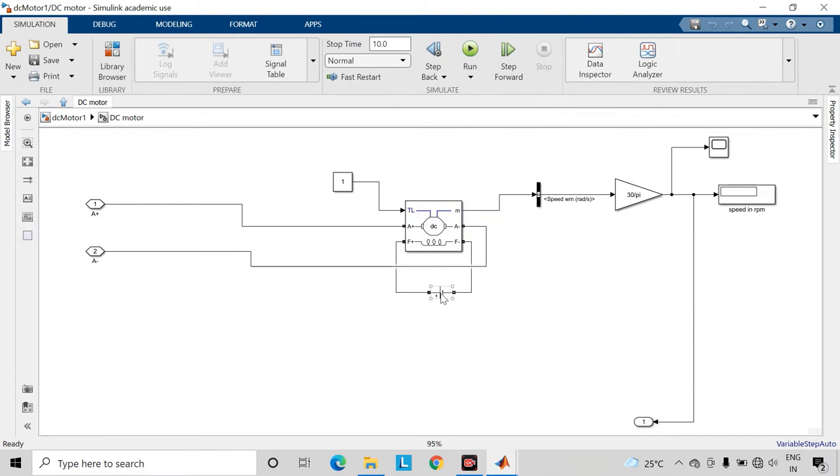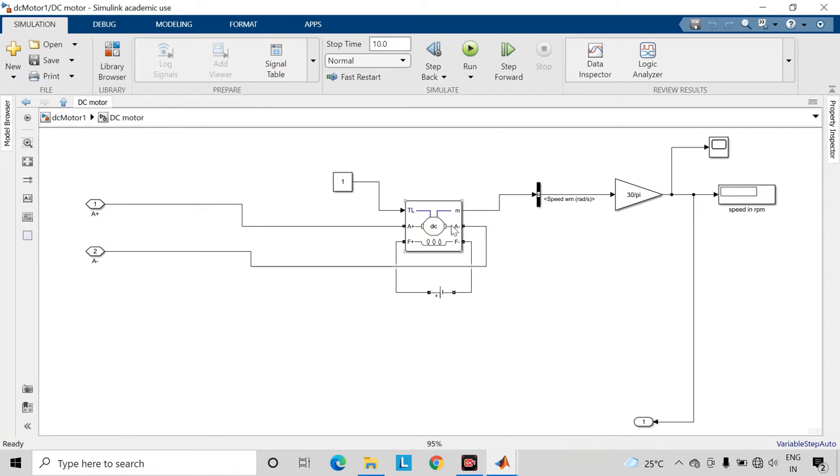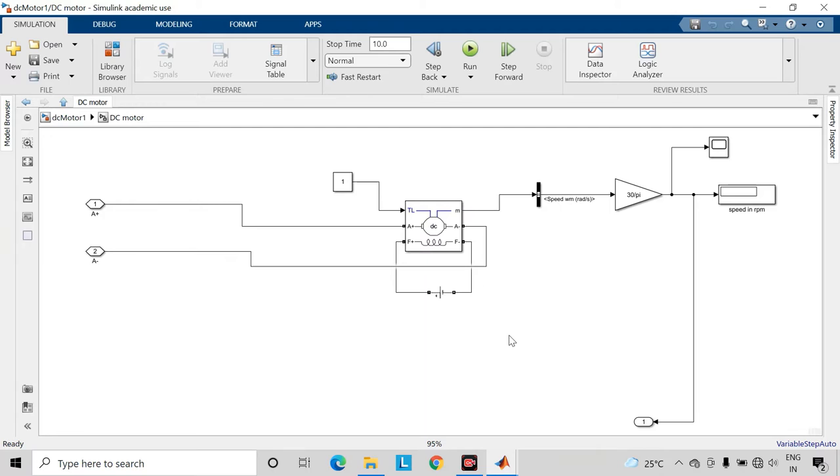So here I have connected 300 volt supply to the field terminals of the DC motor and then the output of this buck converter is connected here to the armature terminals of this DC motor. In case of armature voltage control method, we can control the speed of this DC motor below the rated speed.